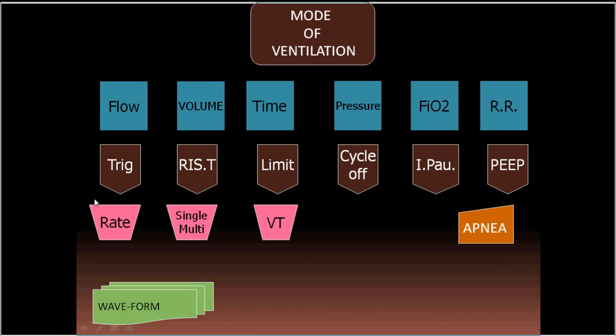In CPAP mode, the control variables show nothing preset except the pressure. There is no preset flow, no preset volume, no preset inspiratory time — only a pressure in the form of the CPAP level.